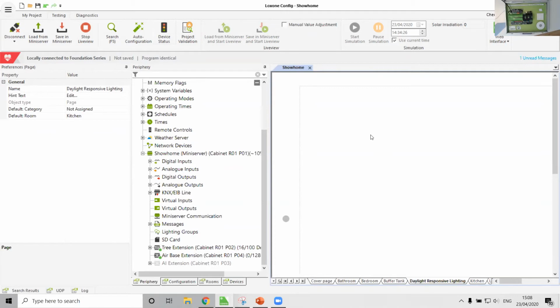Now, obviously, when we're talking about brightness for constant light control, ideally, we should be measuring brightness from the desk. This is the best place to measure brightness from. So it would be ideal in an open plan office to have at least one brightness sensor that is at desk height, which, funnily enough, this one is. Otherwise, if you do have a motion sensor, a brightness sensor on the ceiling, you can still use it. It will be capturing reflected or refracted light.